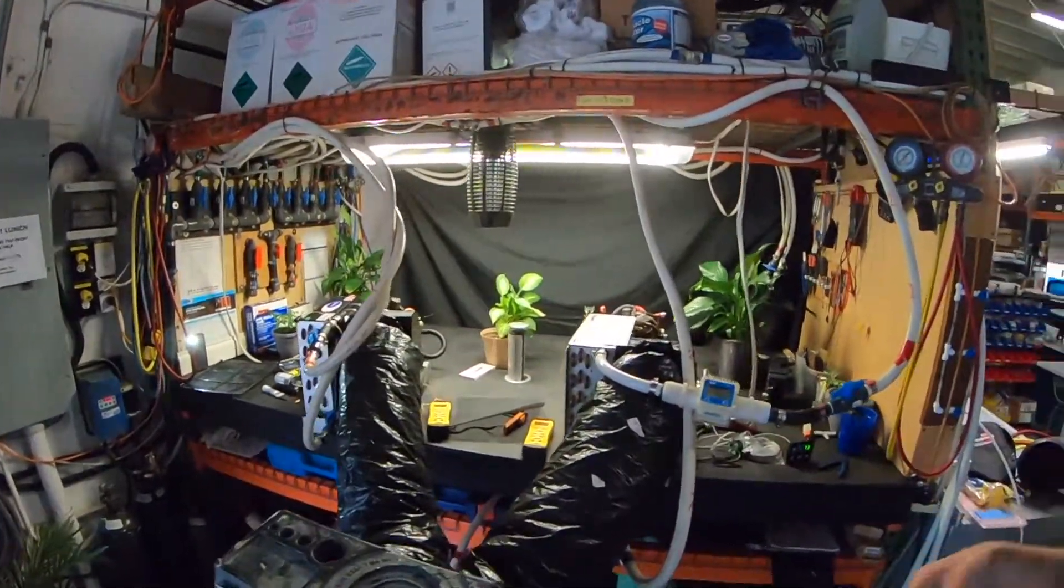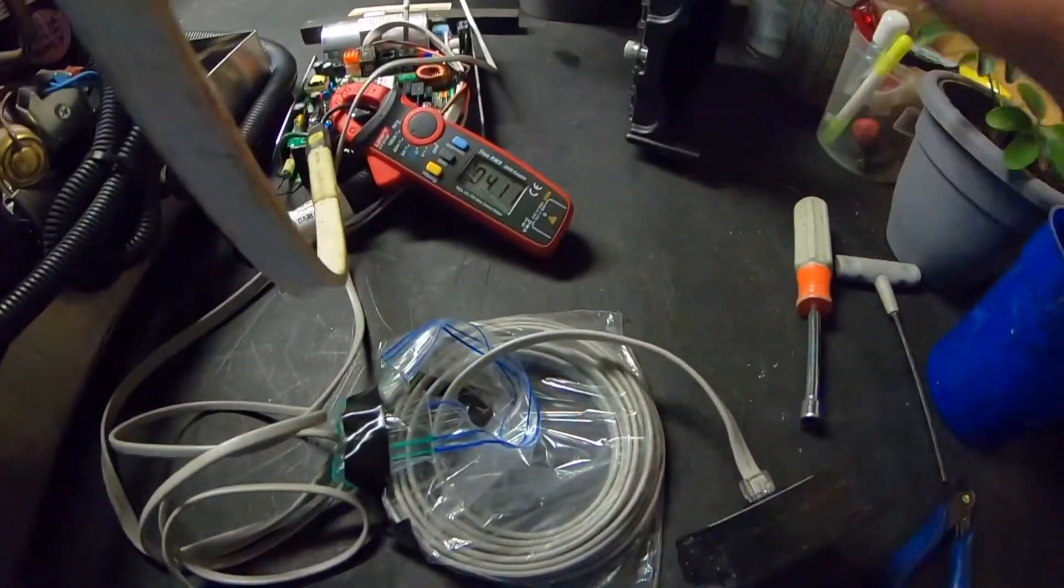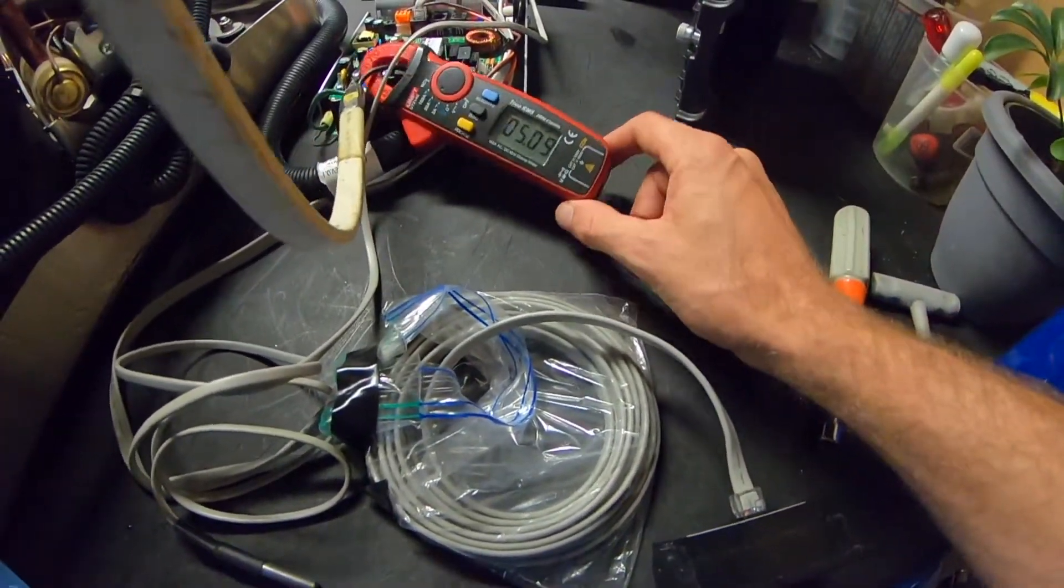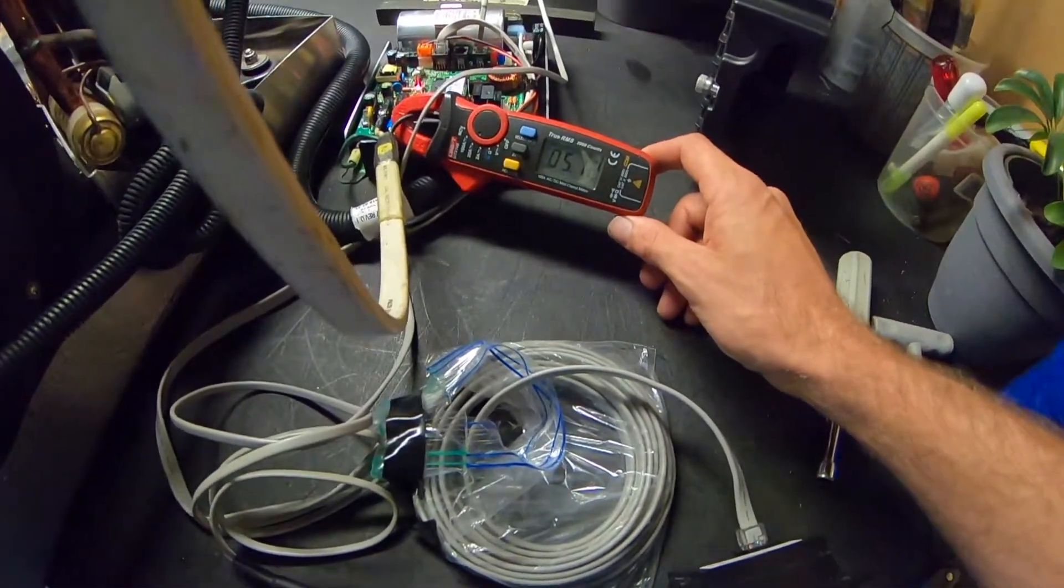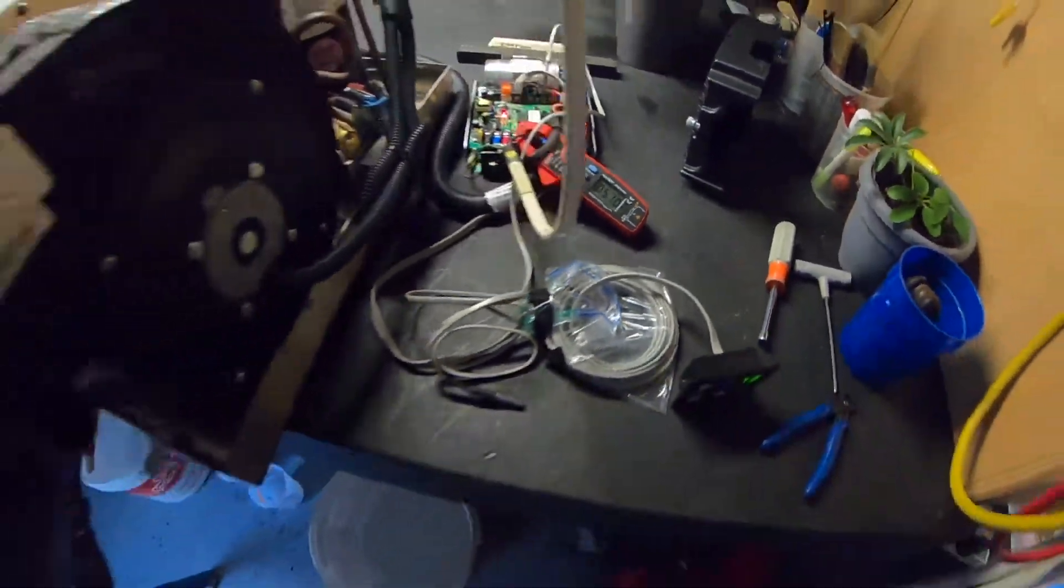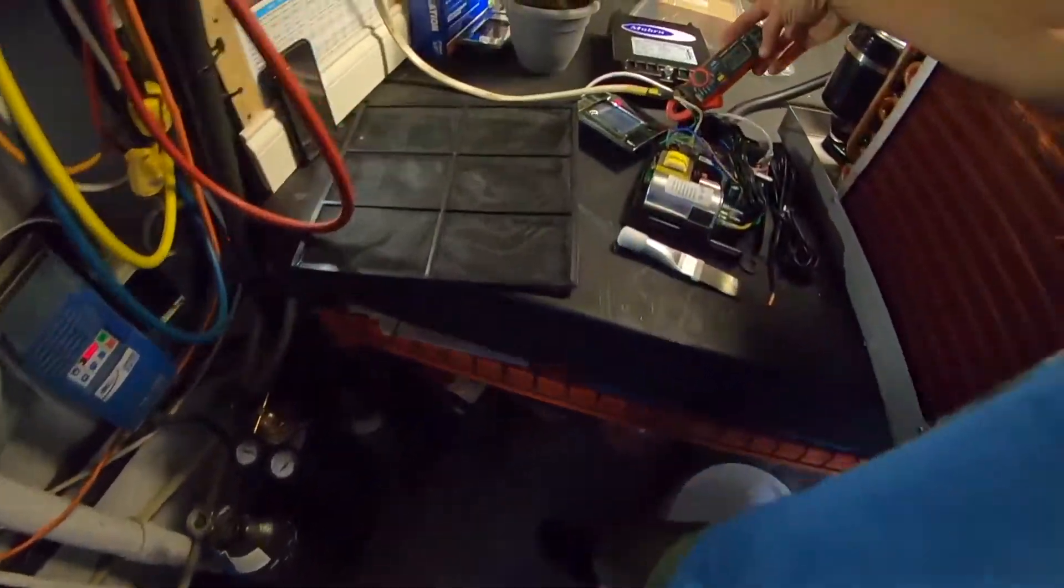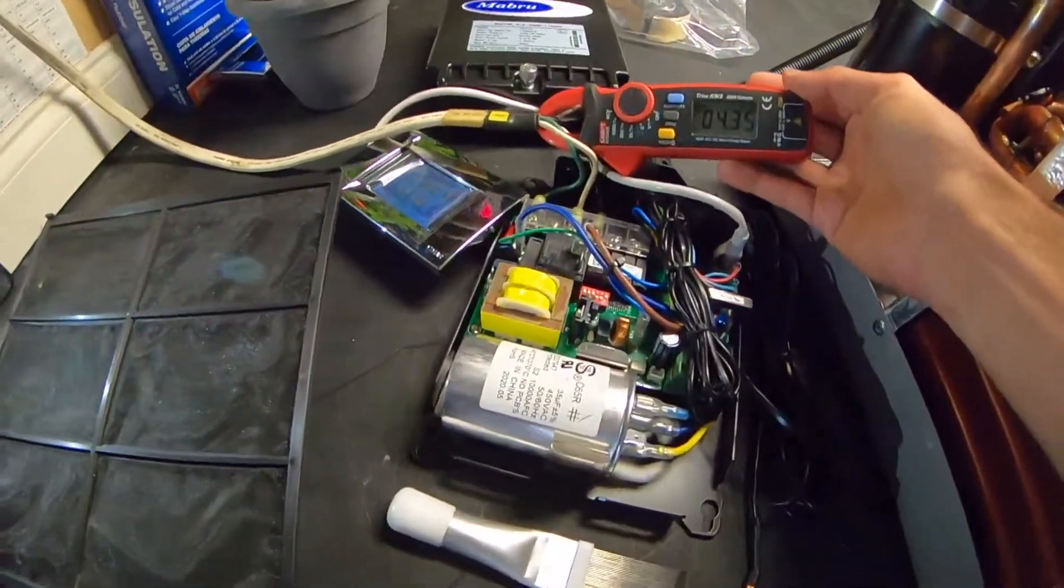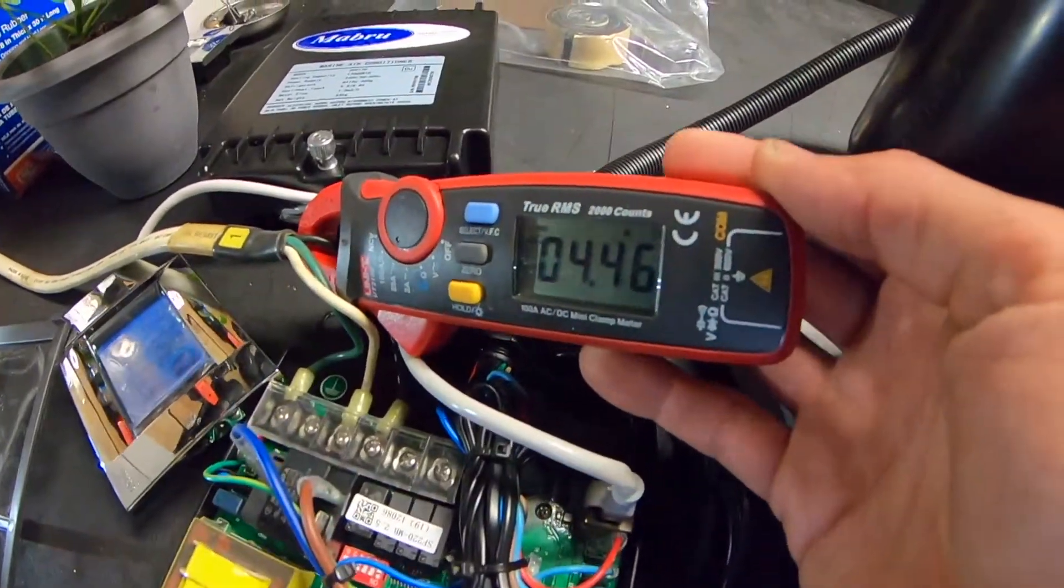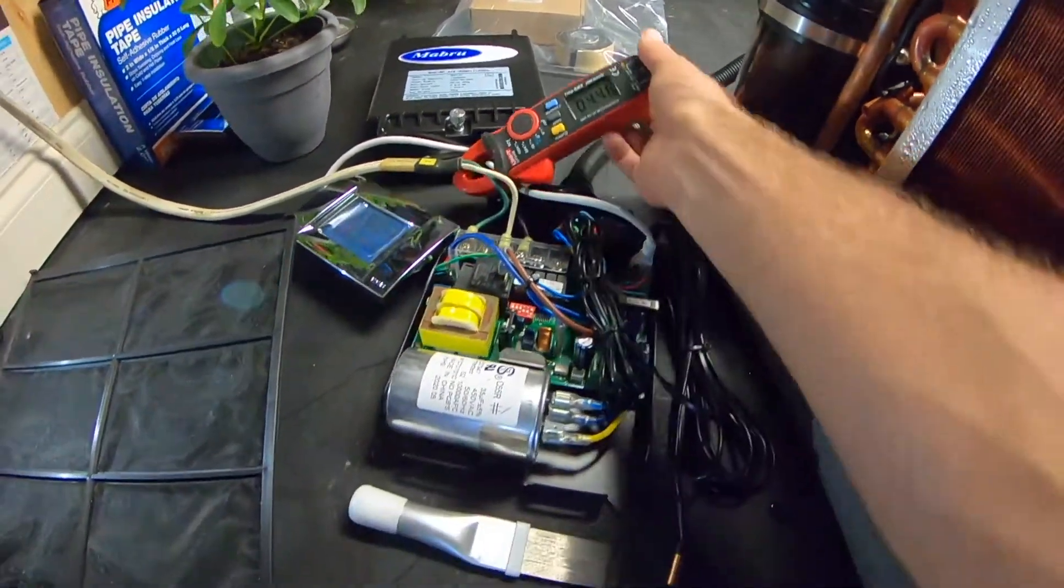Now let's talk about amperage draw. Coming over here to this unit, once again keep in mind it's a 16,000 BTU. This unit is drawing 5.1 amps. This is at 230 volts, that's 16,000 BTU. Then we have our unit, it's a 17,000 BTU. We're drawing 4.5 amps. So we're drawing half an amp less.